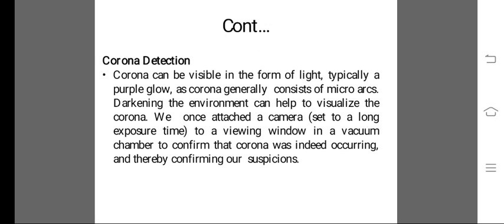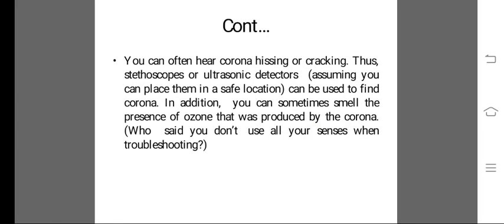Corona Detection. Corona can be visible in the form of light, typically a purple glow, as corona generally consists of micro arcs. Darkening the environment can help to visualize the corona. We once attached a camera to a viewing window in a vacuum chamber to confirm that corona was indeed occurring, thereby confirming our suspicions. You can often hear corona hissing or cracking. Thus, a stethoscope or ultrasonic detectors can be used to find corona. In addition, you can sometimes smell the presence of ozone produced by the corona.